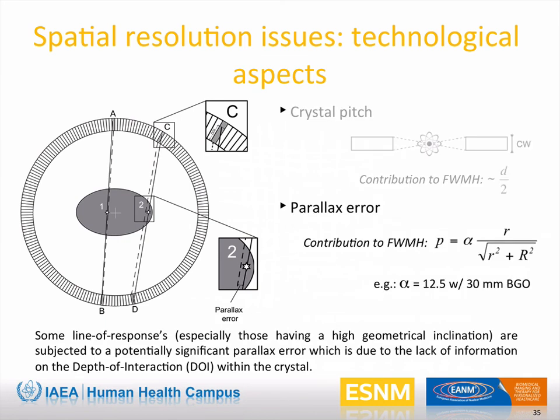The previous considerations are true only for pairs of detectors with negligible thickness. In fact, as the crystals defining the LOR are not lined up, the finite thickness of the crystals comes into play, enlarging the domain of the response function.